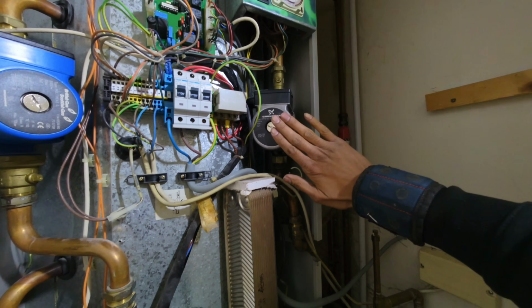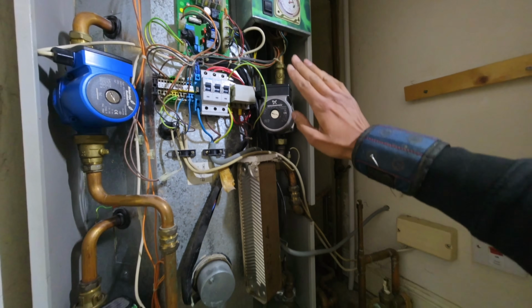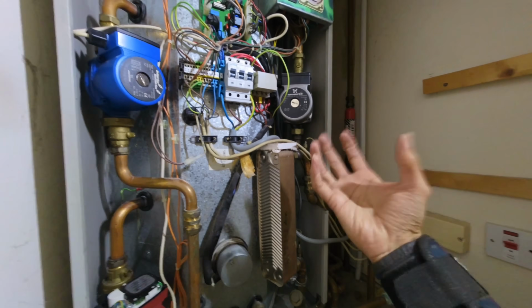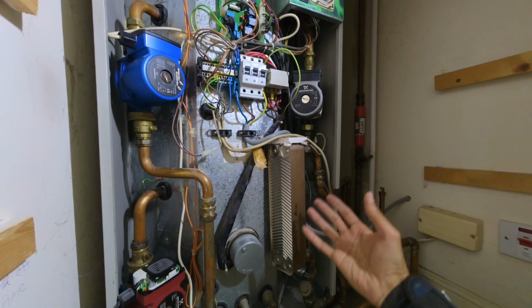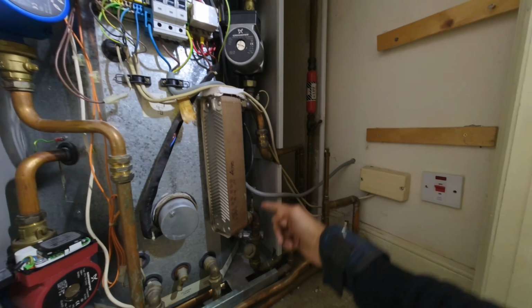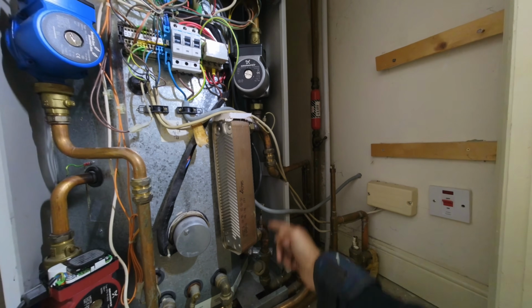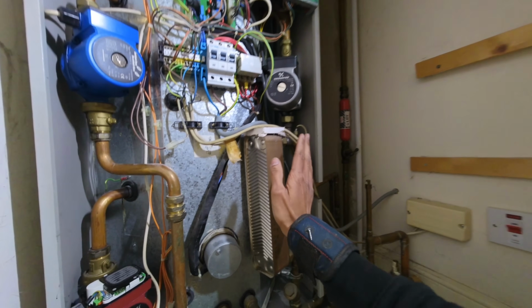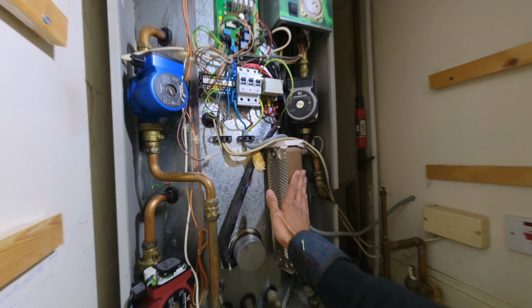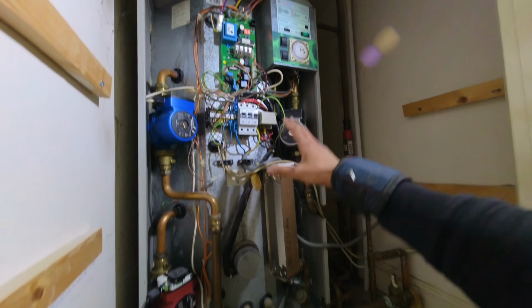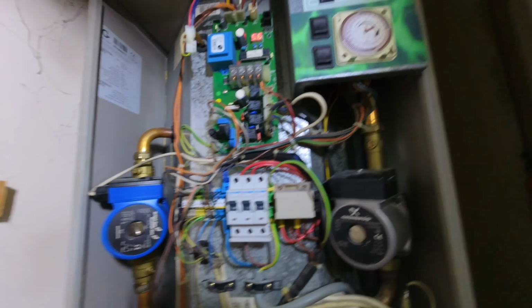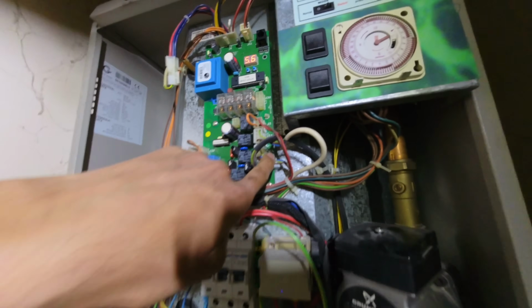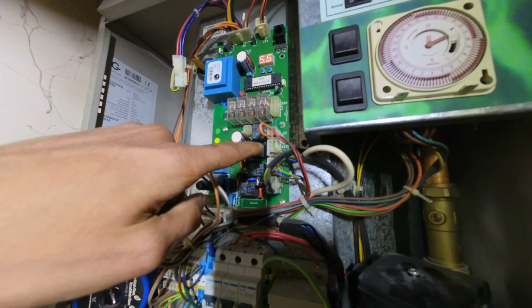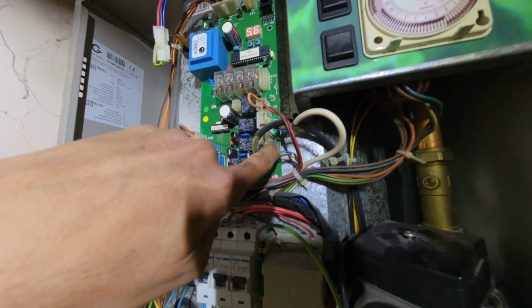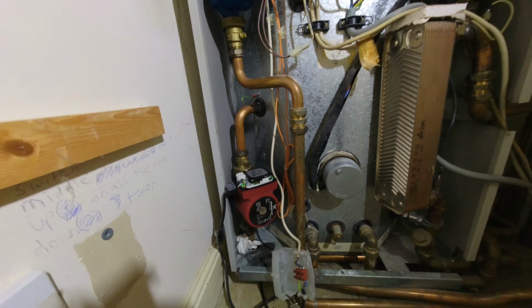The reason this is constantly running, he explained, is because it's trying to get heat but can't. It's trying to find the temperature differential between the flow and return of the plate in order to think it's satisfied, but it's never going to get satisfied because the store isn't hot enough. Now the power to the main boiler pump is J32 - I was checking the wrong one, it's actually J33. J32 is the one going to there.